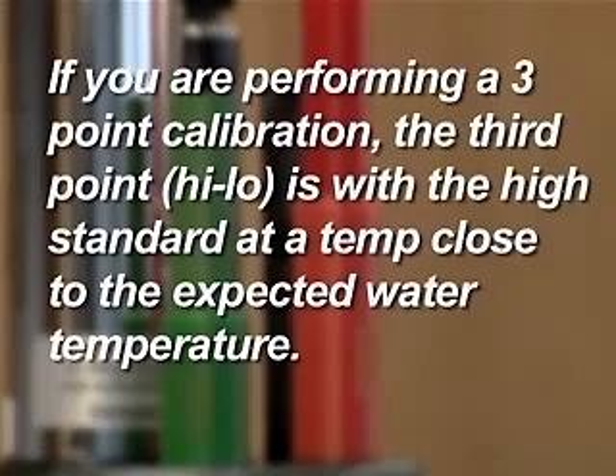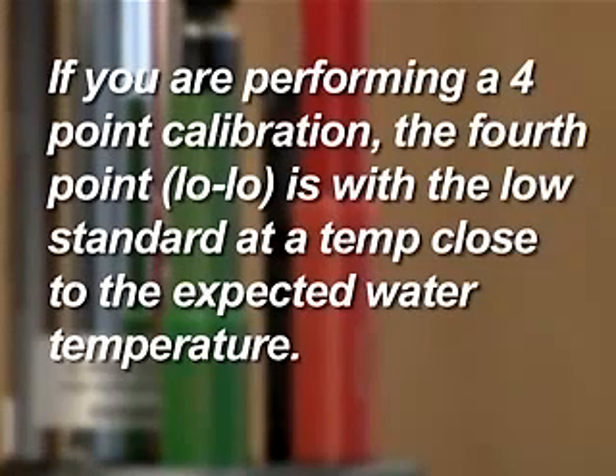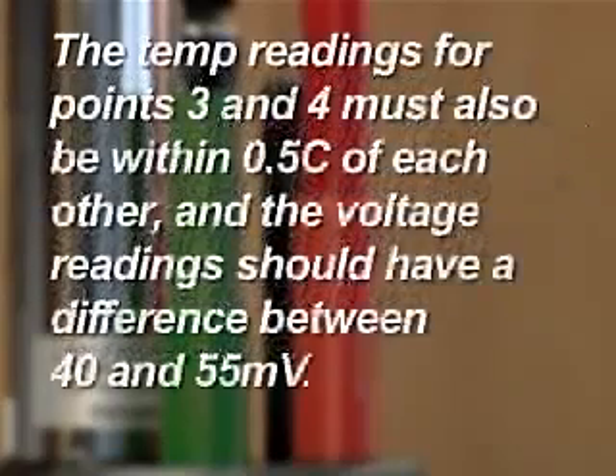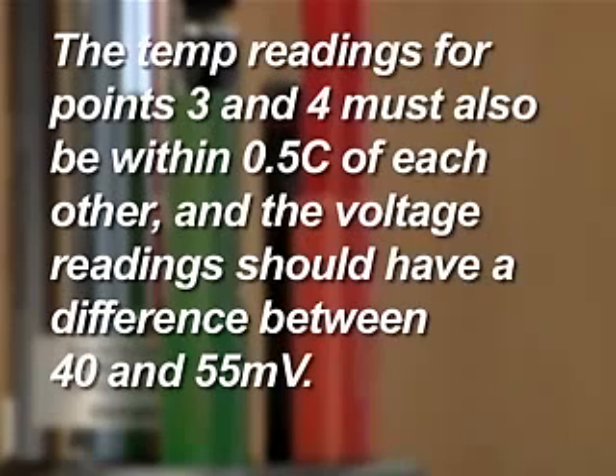If you are performing a three-point calibration, the third point, high-low, is with the high standard at a temperature close to the expected water temperature. If you are performing a four-point calibration, the fourth point, low-low, is with the low standard at a temperature close to the expected water temperature. The temperature readings for points 3 and 4 must also be within 0.5 degrees centigrade of each other, and the voltage readings should have a difference between 40 and 55 millivolts. The chloride sensor is now calibrated.